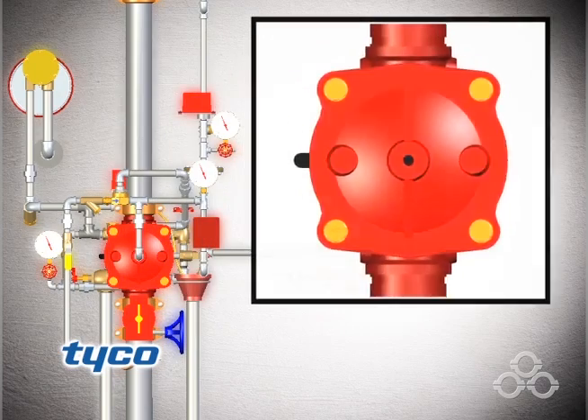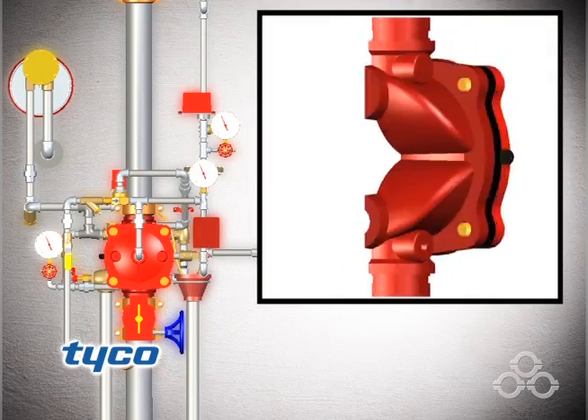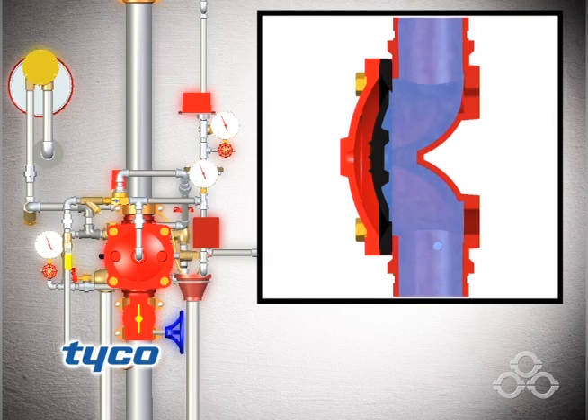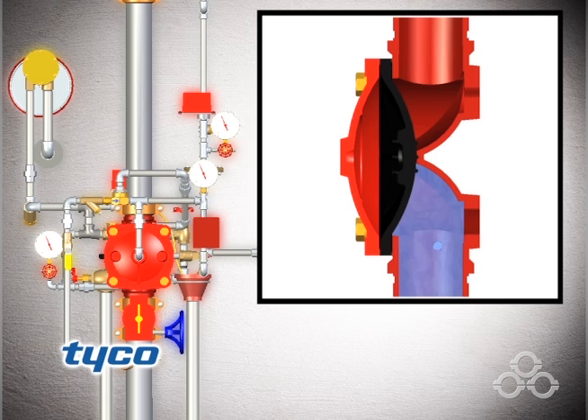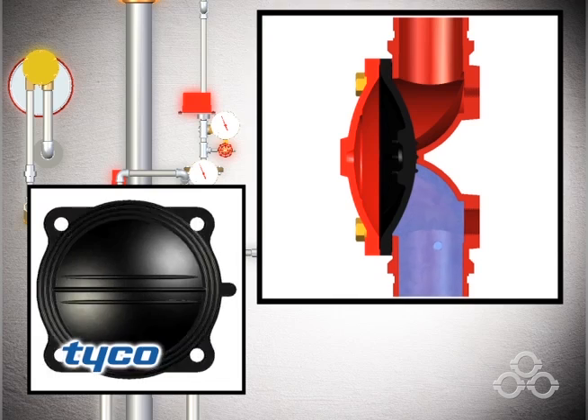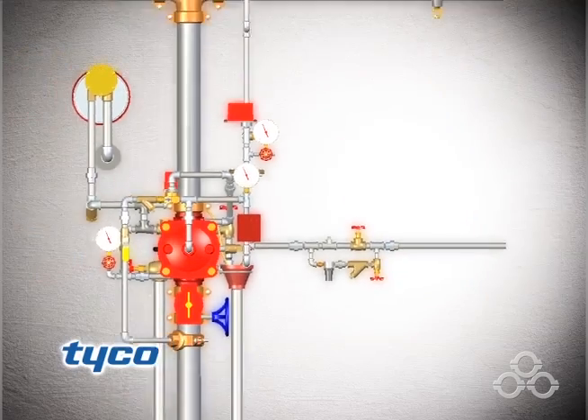The central component of the system is the Model DV-5 Deluge Valve, a diaphragm-style automatic water control valve used in deluge pre-action and special types of fire protection systems. Its single moving part, the diaphragm, depends upon water pressure in the diaphragm chamber to hold the diaphragm closed against the water supply pressure.